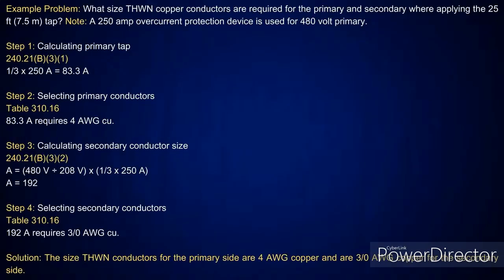Now, here's one that I'm looking at where I have a transformer within the tap. In this case, we're telling you we want you to size the conductors for the primary and secondary, where you have a 25-foot tap. We also put a little note on here so you know what we're doing. You have a 250 amp overcurrent protection device that's used for the 480 volt primary. This way you can size this. We give you all the information you need upstream to be able to do it.